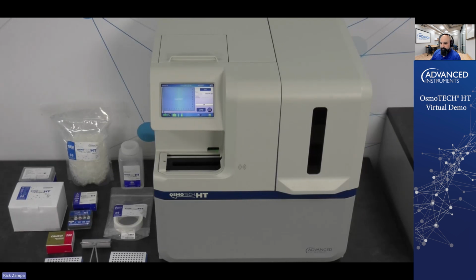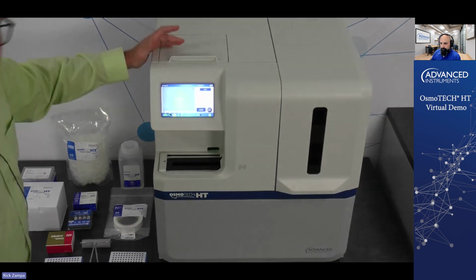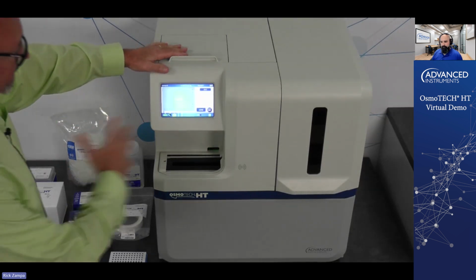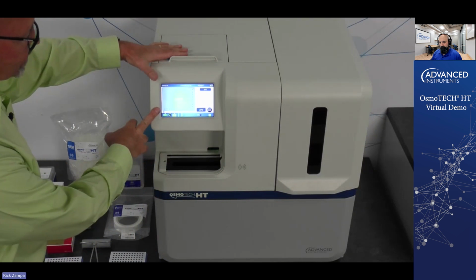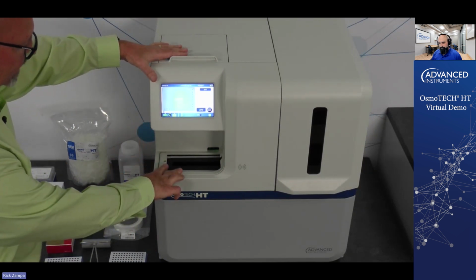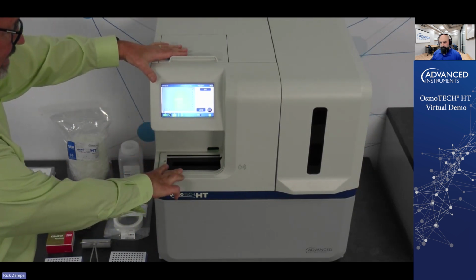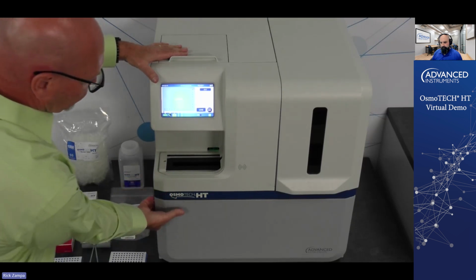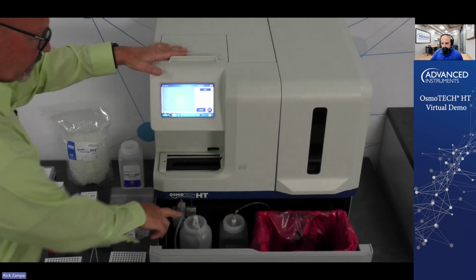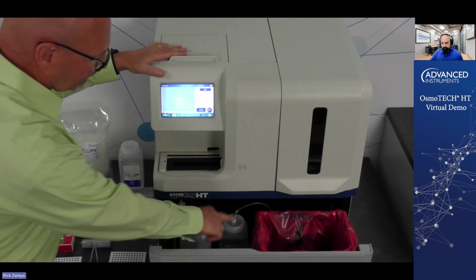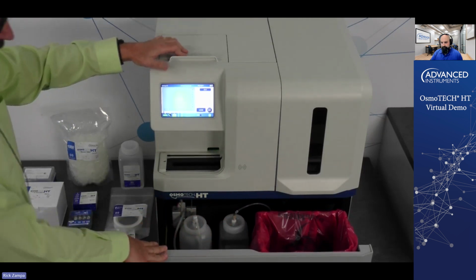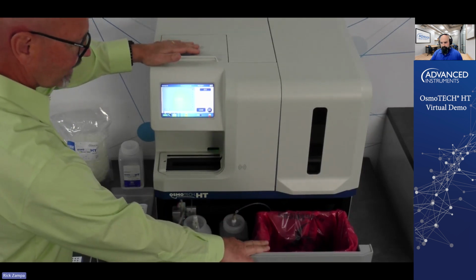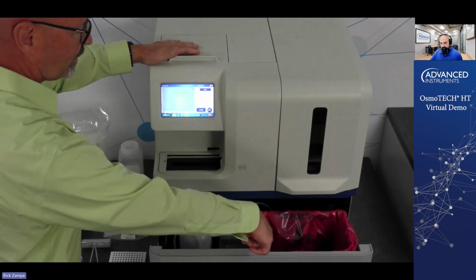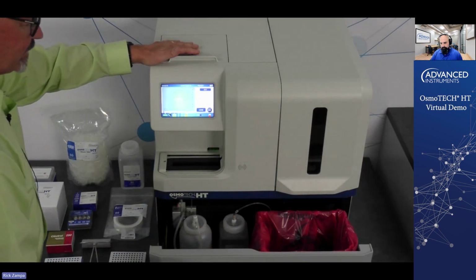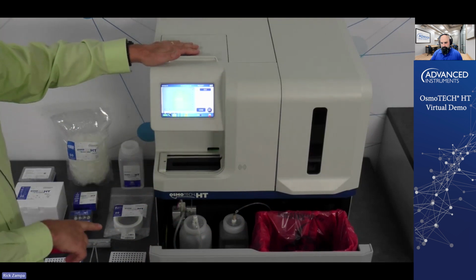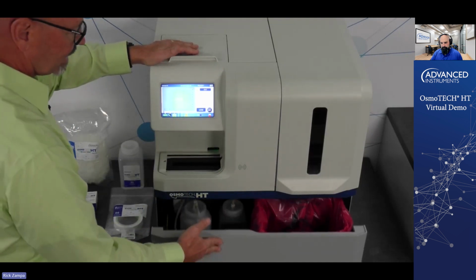But this is the OsmoTECH HT instrument we have here. As you can see, right here, you have a large touch screen display. You have the belt where we're going to load in the plate for the testing. Down here you have a drawer which is used for your waste bottle and your system cleaning fluid. I think you can see that. Also you have your waste bin over here where your used sample cups will go, as well as your used plates when your plates are used. You'll notice it went to red there. I don't think you can see that, but when the drawer is open, it tells you that the drawer is open.